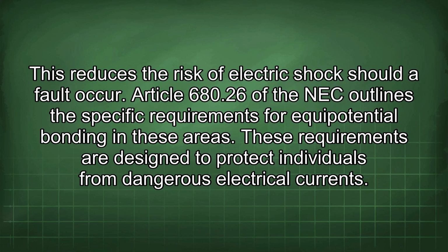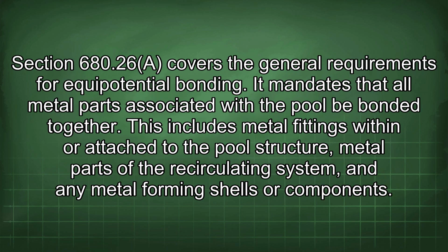Article 680.26 of the NEC outlines the specific requirements for equipotential bonding in these areas. These requirements are designed to protect individuals from dangerous electrical currents. Section 680.26 covers the general requirements for equipotential bonding. It mandates that all metal parts associated with the pool be bonded together. This includes metal fittings within or attached to the pool structure, metal parts of the recirculating system, and any metal forming shells or components.